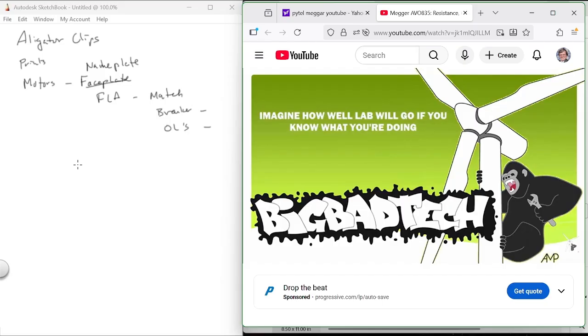A DMM is not the same as a megger. Okay? I don't know how high the voltage is in this one, but I suspect it's in the 500 volt range. But it's at a higher voltage. That device right there that he was holding is not the same as a DMM. All right? It tested 500 volts. And what else did they used to use the old style crank meggers for, besides checking the wiring of a motor?